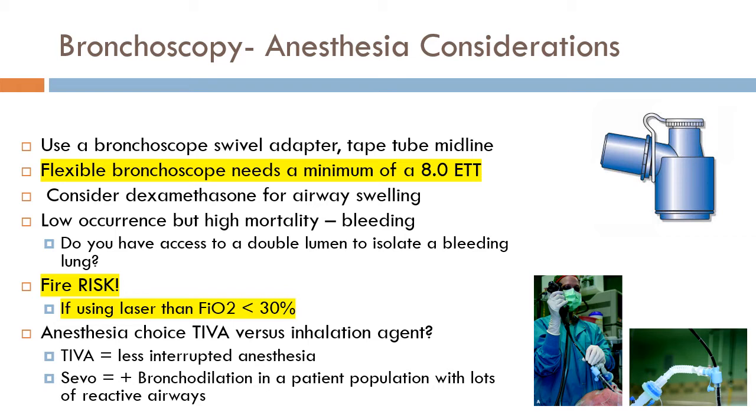Well, that's like asking if the sensor is picking up on what room air should be. I mean, sometimes it comes down to 17%. You're like, huh, wait a minute. If it was 17%, I think I would be dead, right? But we click through it, and then the machine just assumes that the starting room FiO2 is 17% when it's not. So then that means that when you're measuring the FiO2 during the procedure, when it has to be under 30, you're probably several points above 30.